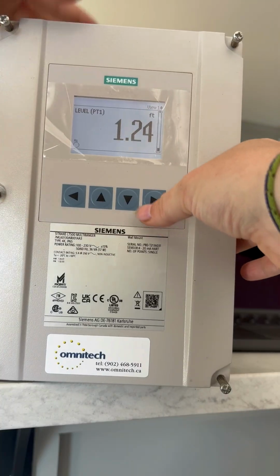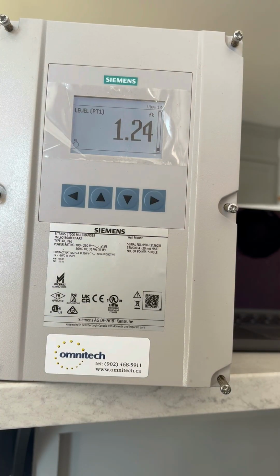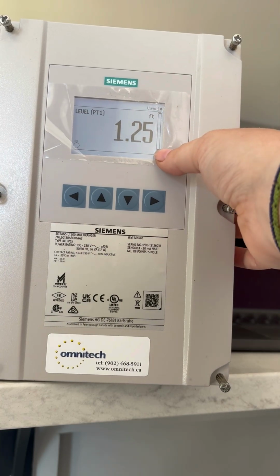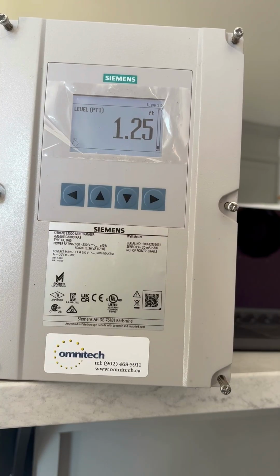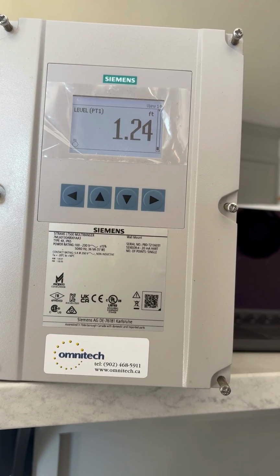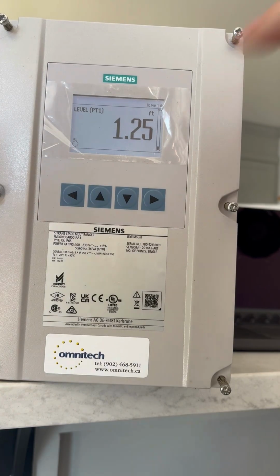Right now, I just have the hydrostatic in a bucket in my sink, just because I'm doing this display for you. I'm about 1.25 feet deep into that bucket of water, and you can see that that's what we have set up as level. Our unit is set for 0 to 12 feet, which means our 4 to 20 milliamp signal is also 0 to 12 feet, scalable throughout that 4 to 20.